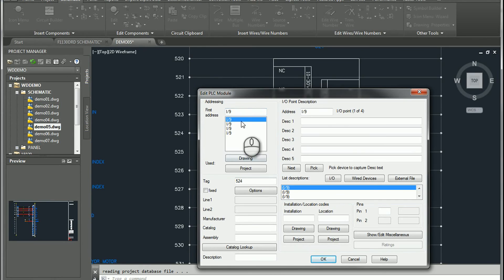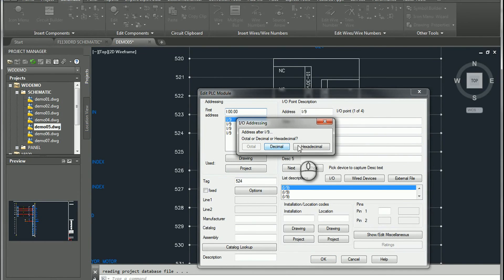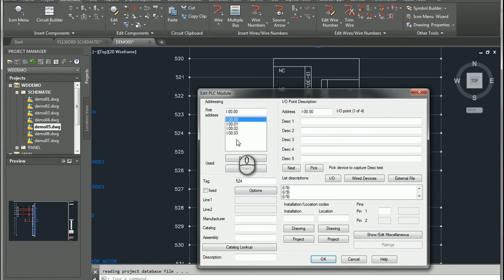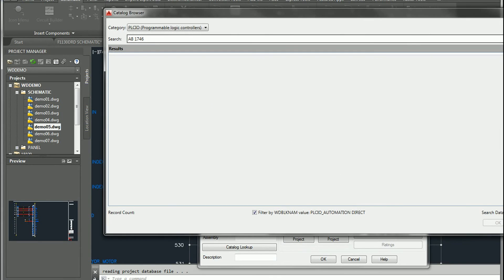We can see the four IO points are in here. If I want to, I can clean up just the first one by putting in the addressing I'd like to see. When I exit the cell, it asks for my addressing and automatically fixes the remaining ones. Each one of these allows us to put our own descriptions in, just like any other PLC. Going to Catalog Lookup, we can put any additional information in there that we need for our PLC IO.